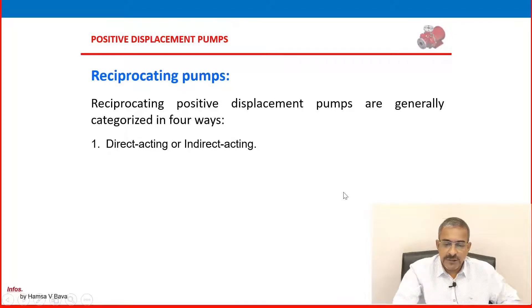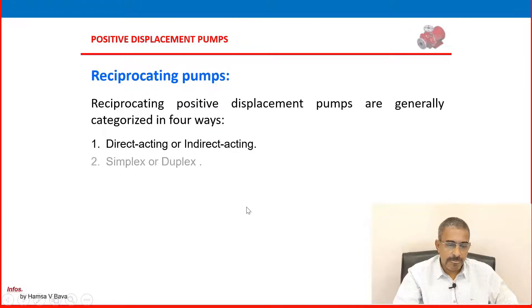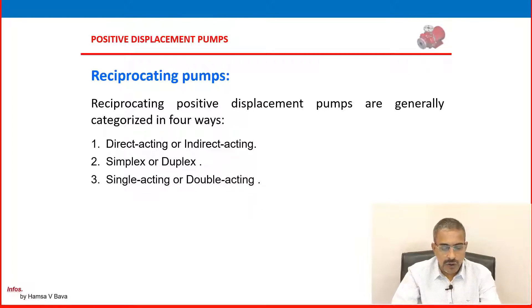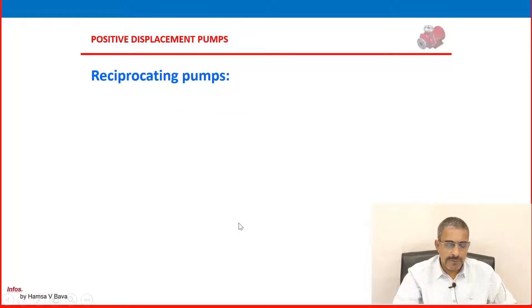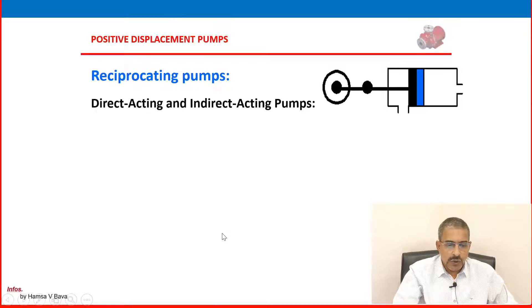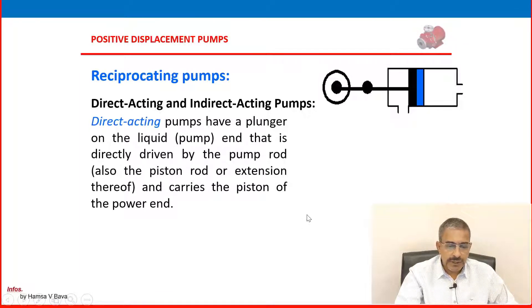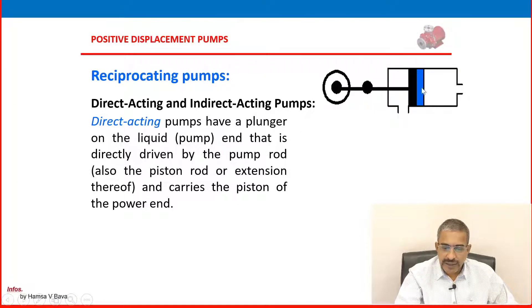Reciprocating positive displacement pumps are generally categorized in four ways: direct acting or indirect acting, simplex or duplex, single acting or double acting, and power pumps. Power pumps are not commonly used, so we will discuss the other three. In direct acting pumps, the pump has a plunger on the liquid end that is directly driven by the pump rod — the piston rod extension — and directly carries the piston at the power end.